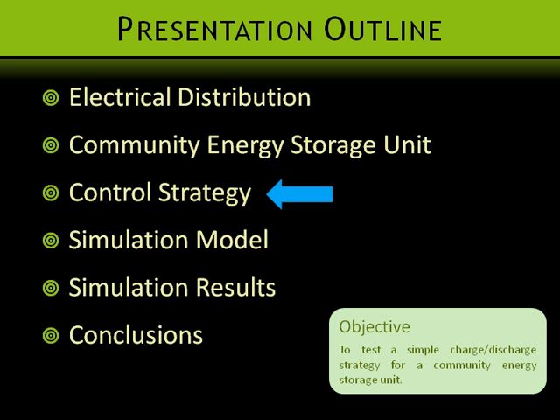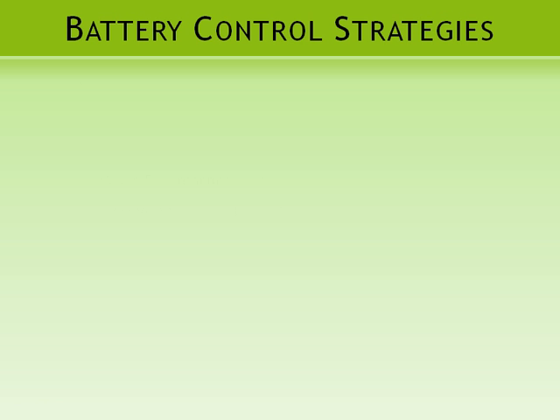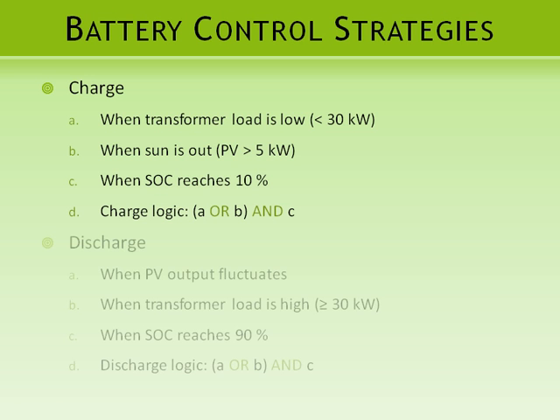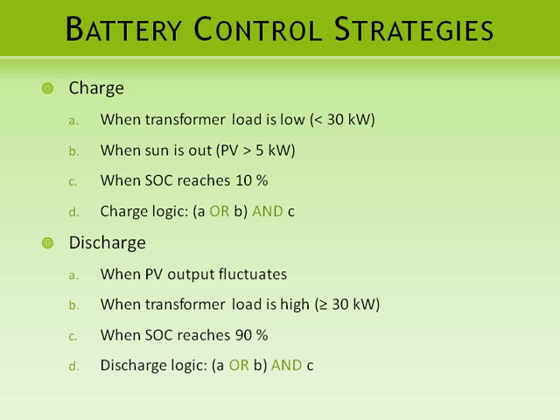Let's take a look at the control strategy used for the storage unit. The unit charges when the transformer load is low or when the sun is out. In either case, the state of charge must have reached 10%. The unit discharges when the PV output fluctuates or when the transformer load is high, which is considered to be above 30 kW. Also in either case, the state of charge must be at least 90%. Although these strategies are preliminary, they help to quickly size the storage unit and give a first look at what the demand will be.